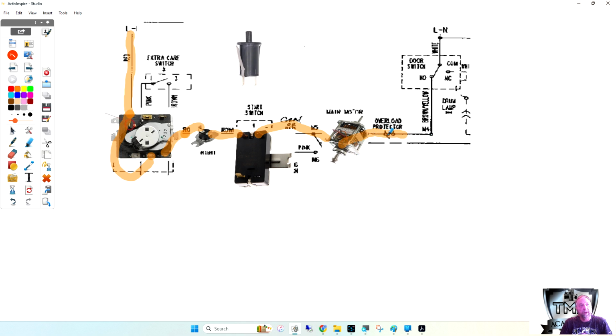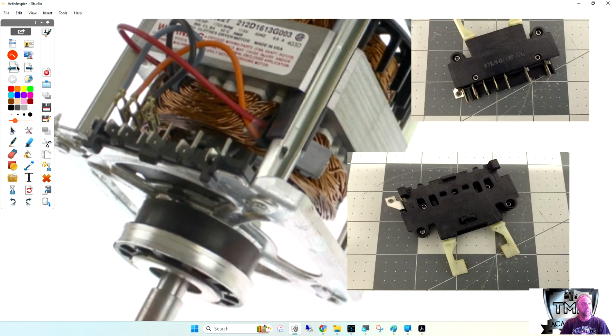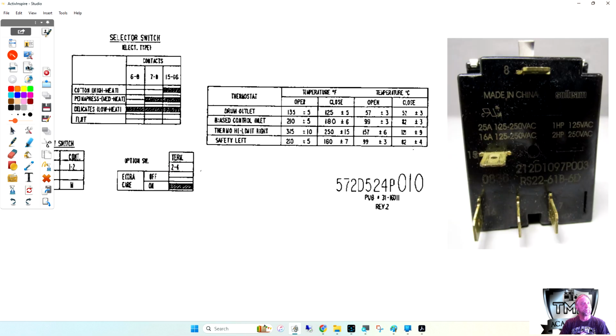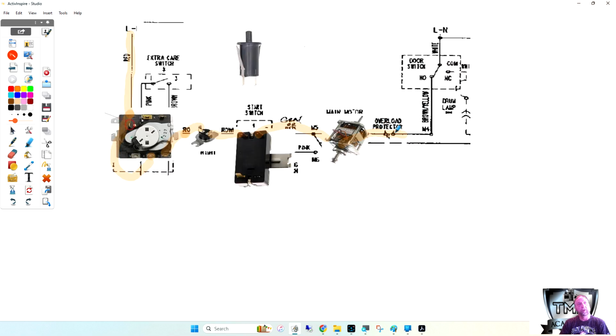The overload protector is not a separate part. It is internal to the motor. It is drawn in the diagram to let you know that it's there, but it's not a part you could replace separately. It is part of the centrifugal switch at motor assembly. If we look at this motor here, this little piece right here with the orange and red wire on it is the overload that you are seeing in the wiring diagram. So that overload is right there. Pin 4 is on the motor, so actually the motor would stretch this far.